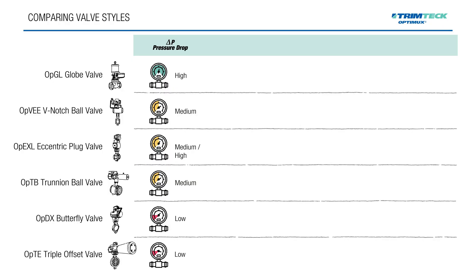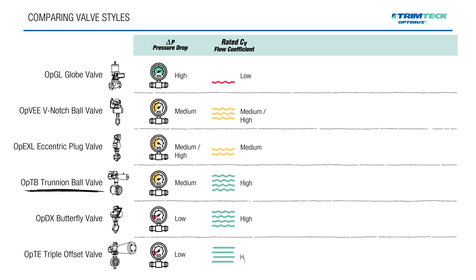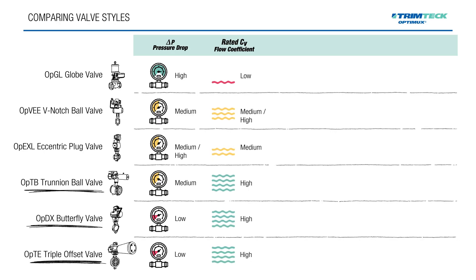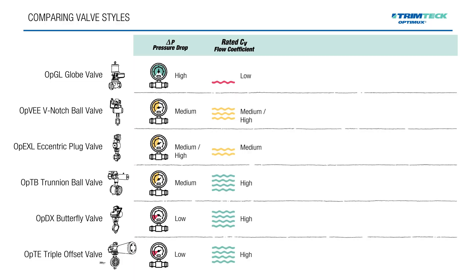Next, let's talk about rated CV or flow capacity. As you may remember from our What is CV video, CV measures how much flow a valve allows under specific conditions. Trunnion ball and butterfly valves tend to offer the highest rated CV values, ideal for large flows at lower pressure losses. Globe and eccentric plug valves typically have lower rated CV per size, but provide excellent control.